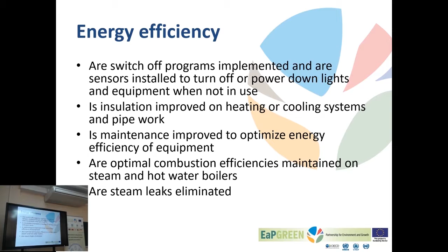Maintenance to keep energy efficiency of equipment high. Preventive maintenance on motors, on bearings, is something to think of. Talking about boilers, which we will do in a minute, combustion efficiency, air-to-fuel ratio is something, exhaust gas temperature is something to watch. Elimination of steam leaks might also be an issue.